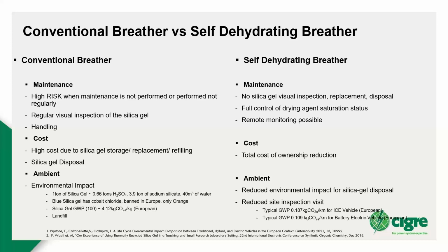With the self-dehydrating breather, the advantages are: you do not need regular visual inspection, you can cut it down; you do not need to replace it; you do not need to dispose of it. You can see the status and percentage saturation levels of the silica gel, and remote monitoring is also possible. And when we look at the total life cycle cost of ownership, there is a significant reduction in cost.